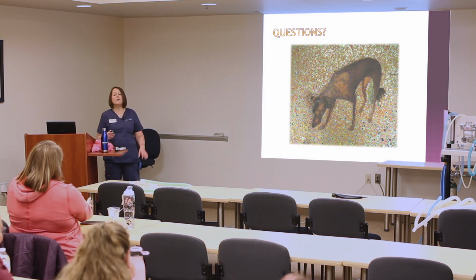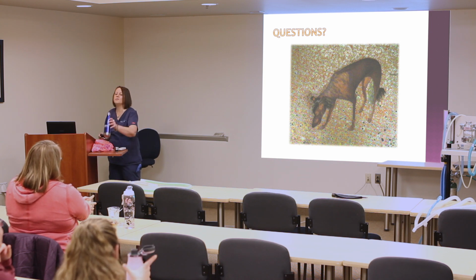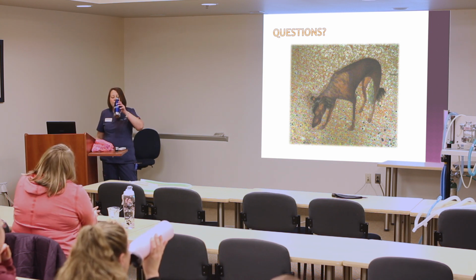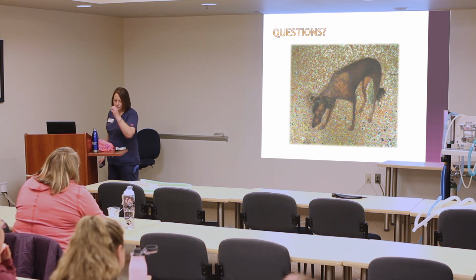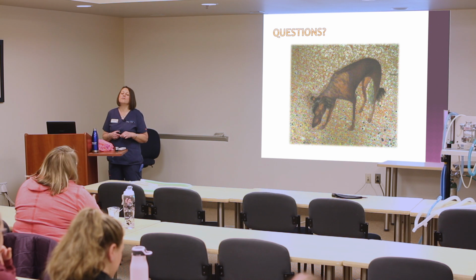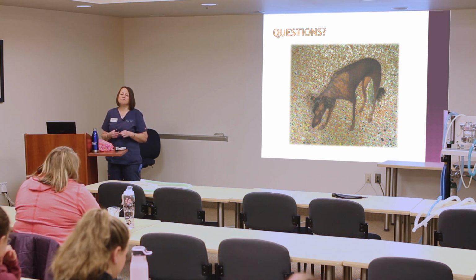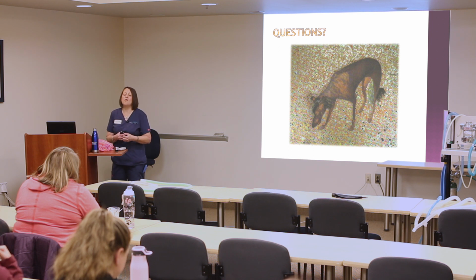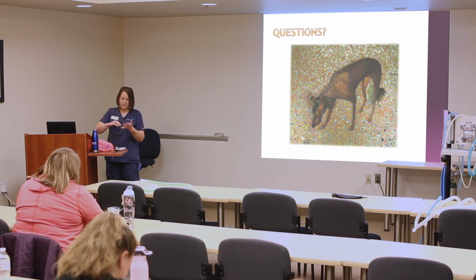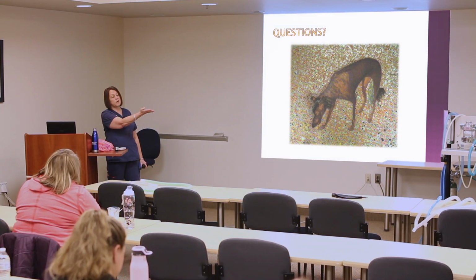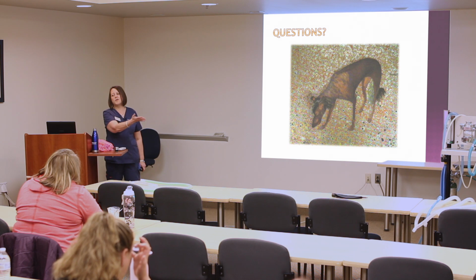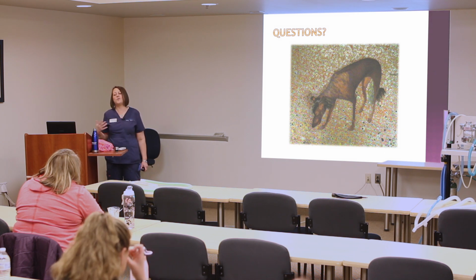Question here. Oh, yes. Our machine in internal medicine, I noticed on Friday the sorb hasn't been changed since September, but it's not purple. Yeah, so I think you guys are supposed to be using the old sorb. So when you're monitoring carbon dioxide for all of your cases, as long as you're not seeing inspired CO2 more than 2 to 5, or your exhaled carbon dioxide numbers are still normal, then technically it's still good. Technically, machine number 5, this one here, because it's hardly ever used, I've actually left the sorb in there for up to a year.